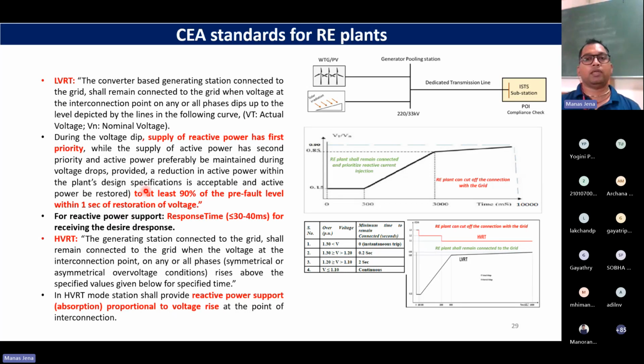This is also very, very important, and this is where I will discuss a few cases. You will see many inverters struggling. Wherever you are giving X megawatt, you suddenly reduce your megawatt and increase your MVAR to support the grid during the fault. Once the fault is cleared, again you should at least reach 90% of the pre-fault power, whatever you were giving as X. So 90% of X megawatt within 1 second. That is very, very important, and that is what is not happening in many cases. So this is about LVRT.